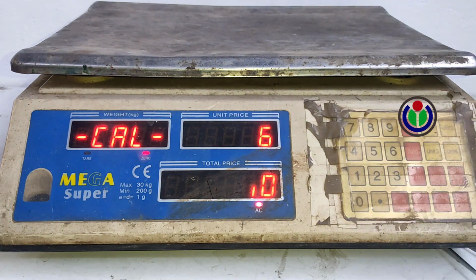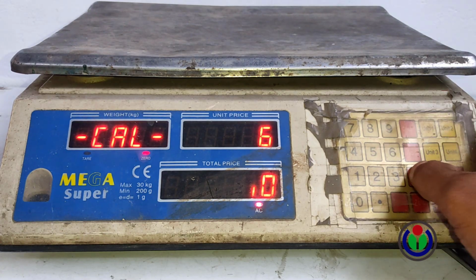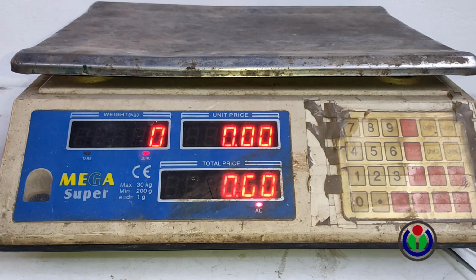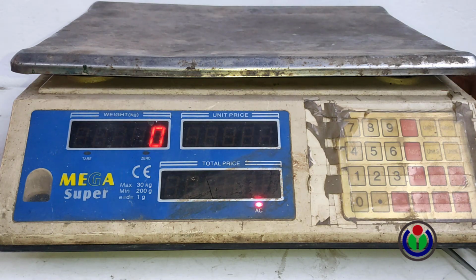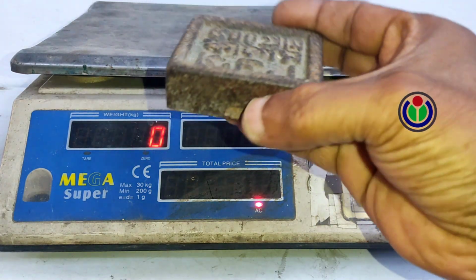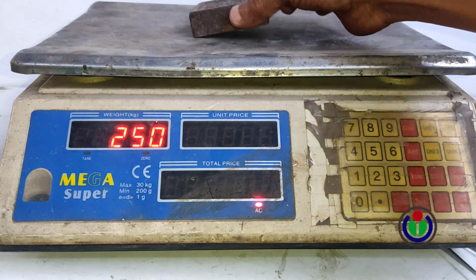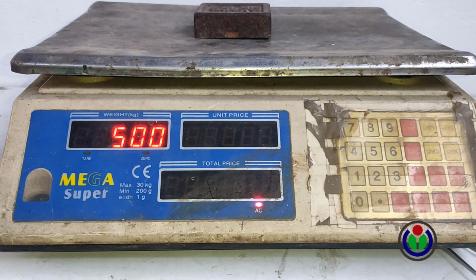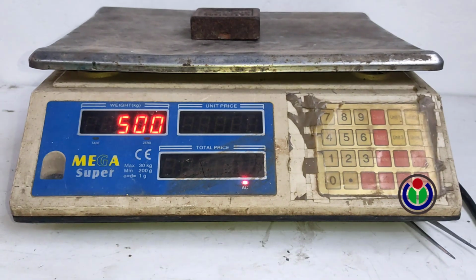Step 6. Keep the information of this step as default and press Tare once. Now I turned off the weight scale and removed the standard calibration weight set. I turned on the weight scale and placed the weight set in the scale tray. The weight of the weight set is displayed as 500 grams, which is correct. The digital scale is now useful for measuring the correct weight.